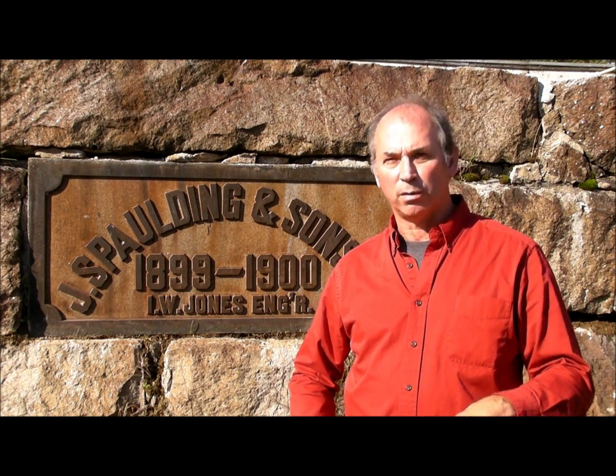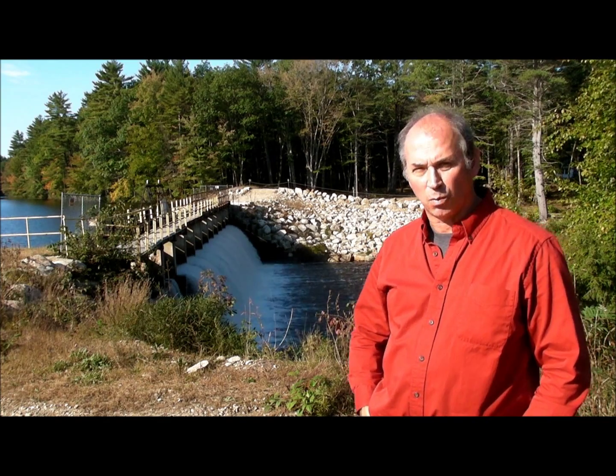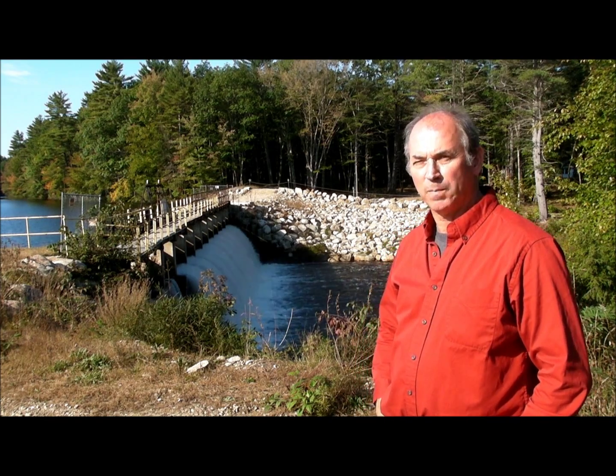We'd like to give you a quick overview of how this hydroelectric system works. It was designed in 1899 by J. Spaulding, and we'll let you know how we've made it work today. Behind me you see the spillway, which most people consider the dam. What creates electricity is head pressure — the difference between the height of the water going in and the height of the water going out. This dam is some 1,500 feet away from the actual turbines upriver and creates a head pressure of 25 feet.